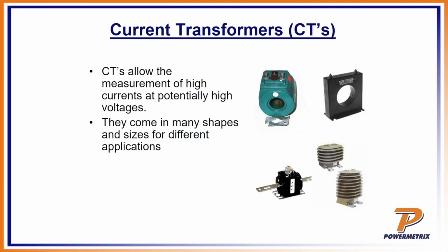So current transformers, CTs. You see the ones at the top, those are the donuts mentioned earlier where you can just run the conductor through the hole of the donut, right? So you can run it through on those top ones. You also see the bar type right there, okay, down bottom left. And when you guys have used our equipment and done a load boost test, that's why the load boost kit has the clamps as well as the drive cable, right? So I know there's some people nodding out there.